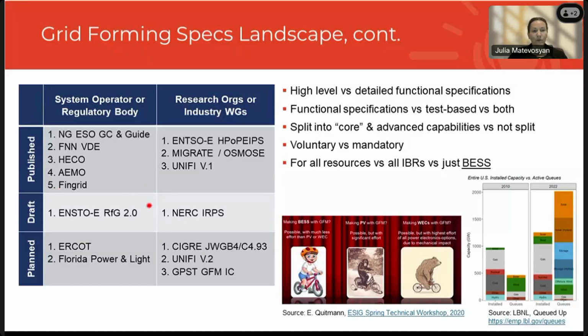There are some drafts on the way. So ENTSO-E currently is working on a draft, which is an update, a grid code change to RfG, and that one has high-level grid forming specifications. NERC IRPS is no longer a draft, so that moves up into the upper column here. And then there are planned specifications. So ERCOT is currently planning to produce a specification for grid forming batteries, and Florida Power and Light is planning to do it as the next step.